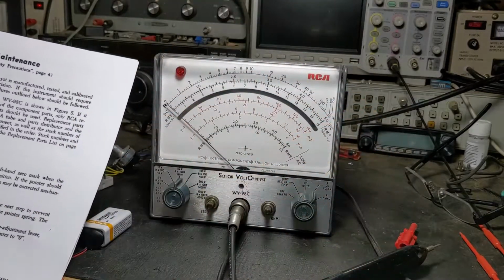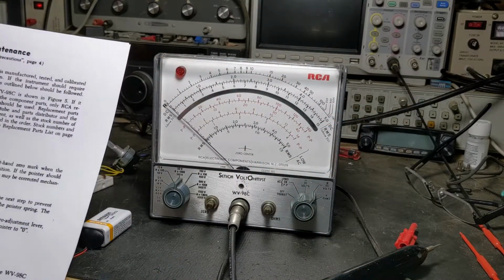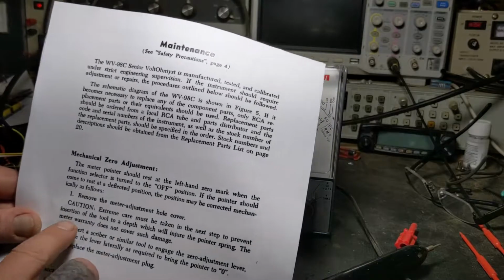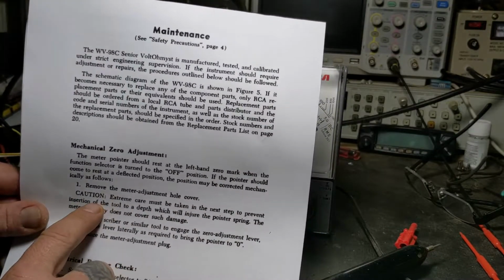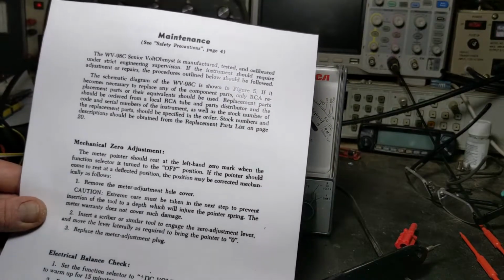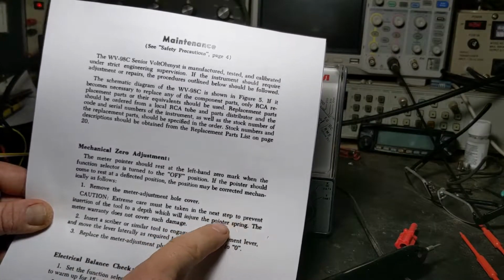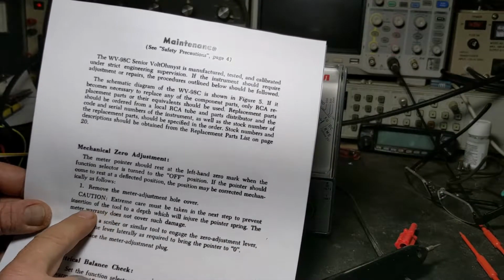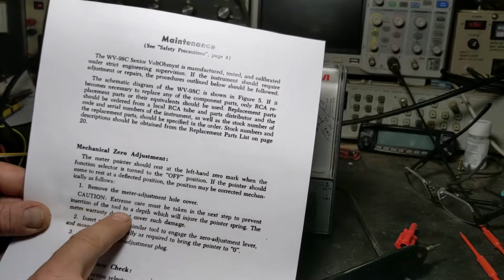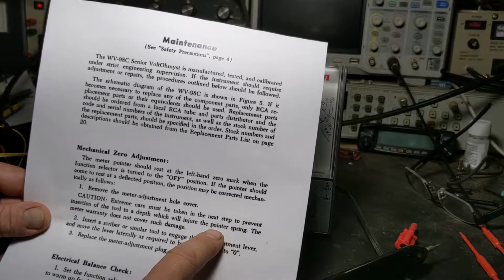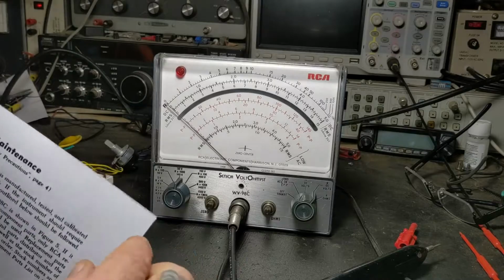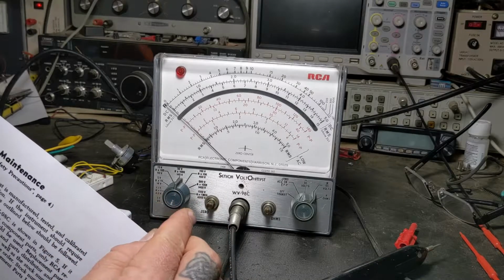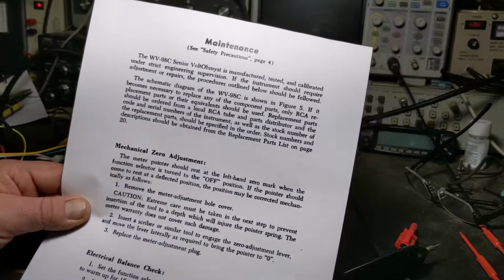But you want to do all that with the meter off, turned off, been off, unplugged, all that. And it tells you here, caution, big word, big letters here. Extreme care must be taken in the next step to prevent insertion of the tool to a depth which will injure the pointer spring. So, don't jab that thing up in there. You can get where you can see it, just barely go in there and touch it if you have to.